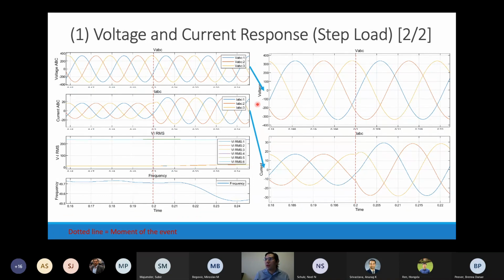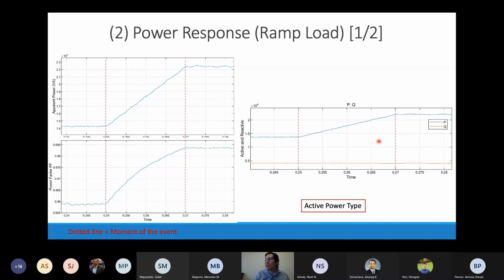In this following figure, I'm showing the same case study, but here we have voltage, current, voltage RMS, and our frequency. But the most important figures to notice are the voltage and the current here. As we can see, we have some small transient when the load kicks in. And thanks to our controller, we were able to continue operation of the inverter in less than a cycle. Here I'm testing a ramp type of load.